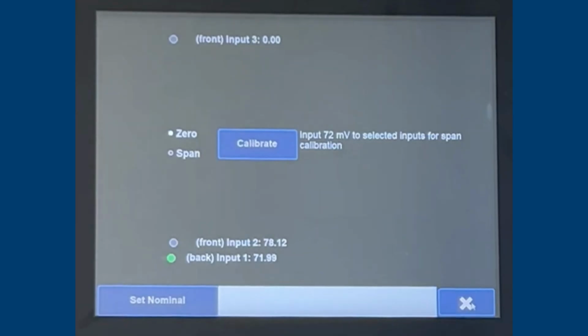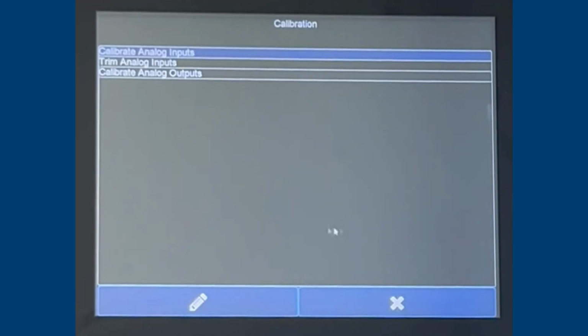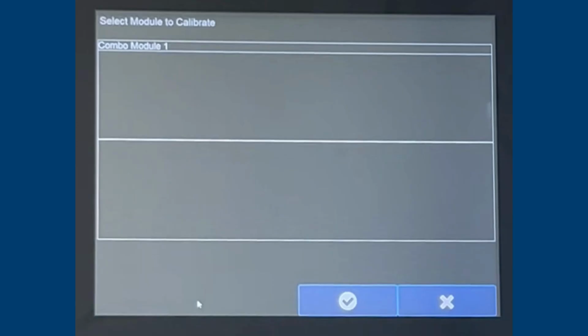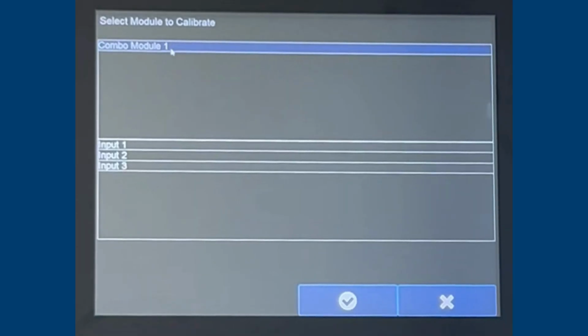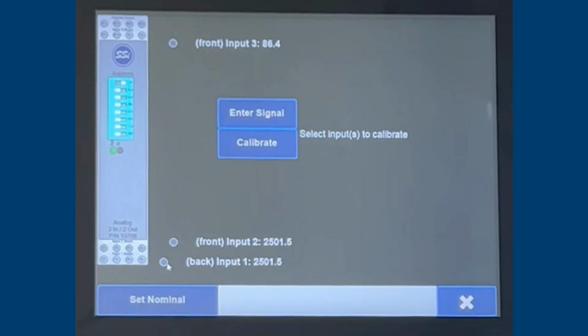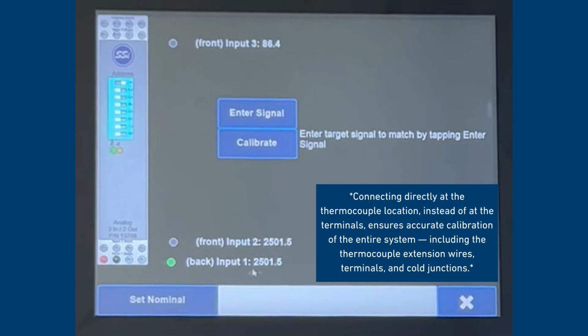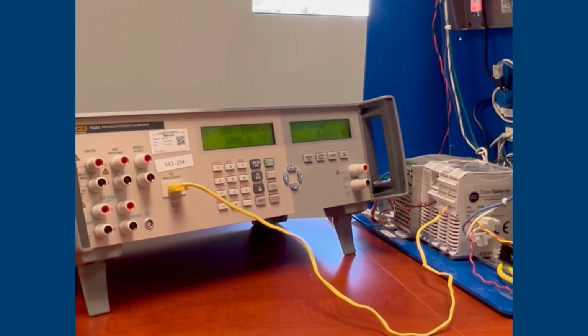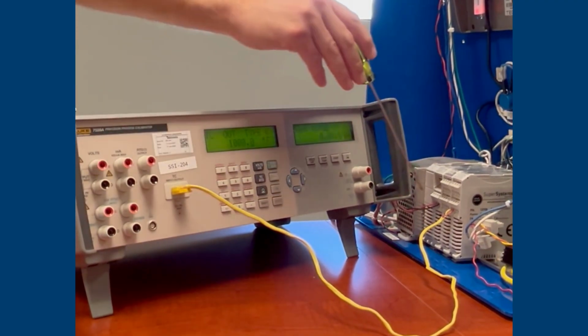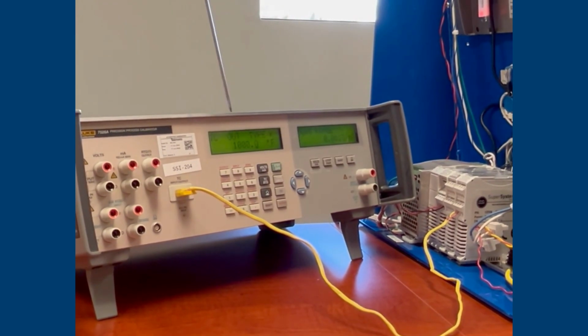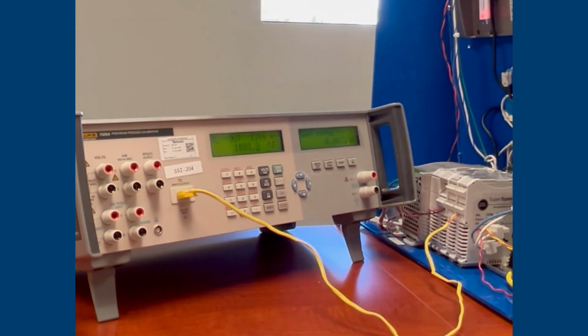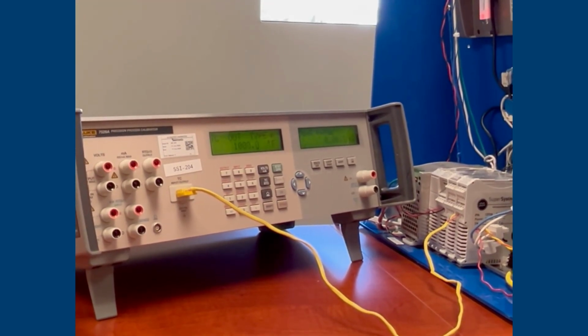If we need to check to make sure that the trim input is accurate, we would select Trim Analog Inputs. Then select the module we are working with if there is more than one. In here, we will select the box we are working with. In our case, we are working with Analog Input 1. We are going to source through a TC wire that is the same as what the input is set for. In this case, input 1 is set for a K thermocouple, so we are going to source through KTC wire to analog input 1. For the trim adjust, we are sourcing through a K thermocouple wire into input 1, and we are sourcing through the K wire 1000 degrees for performing the trim adjust on the analog input module.